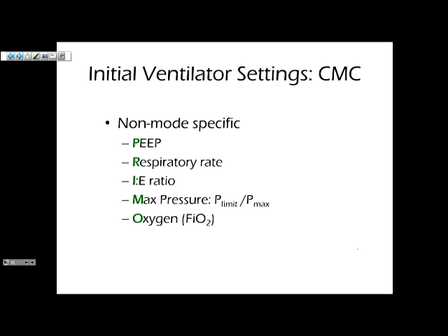It'd be nice if the ventilator companies would all name it the same thing. They don't. They can't possibly make it that easy for us. And you need to understand what I'm talking about here versus other pressure parameters that are not necessarily an intervention, but a monitoring mode. So we can set a monitor and an alarm, or we can even set a setting in pressure control ventilation. We can control that within the mode, but this is outside of the mode. Anesthesia ventilators allow us to set basically an APL valve for the ventilator. So that is key. And then, of course, the FiO2.